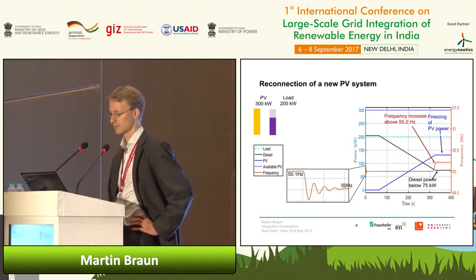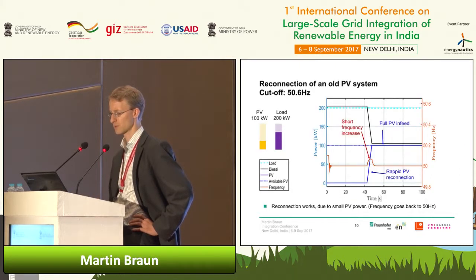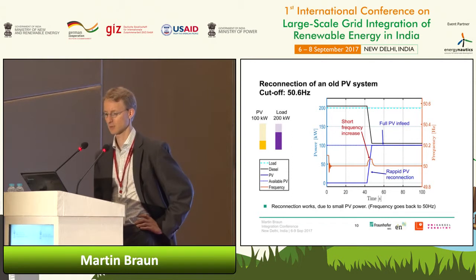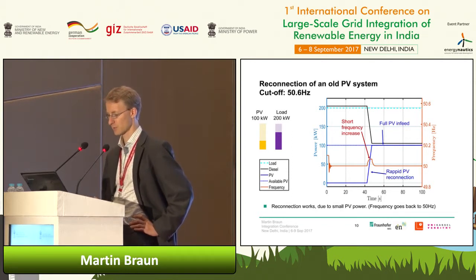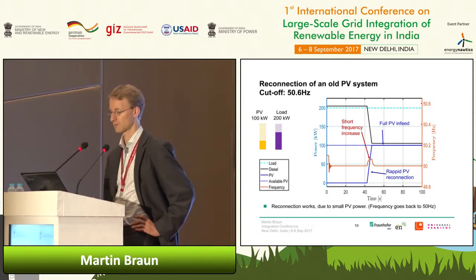Now if you see the reconnection of an old PV system, assuming a 50.6 Hertz cutoff frequency, we see that the increase is much steeper. So the ramping was also not so defined in the older standard. And we can see that there is a short increase of frequency, and the diesel genset is regulated down, so PV is taking over part of the loading from the diesel genset. As PV is just a small number compared to the load, we are still under nominal frequency constellation.